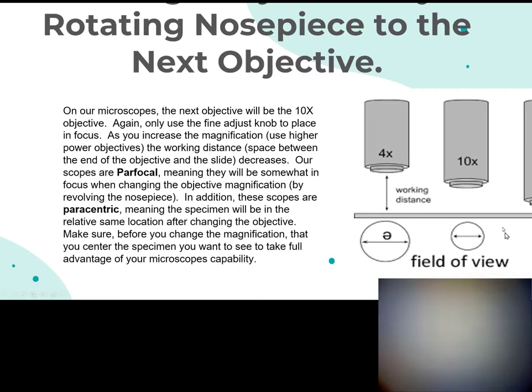Two terms I want you to know: parfocal means that when I start at 4x and swing the objective to 10x, it'll be somewhat in focus already. Paracentric means that when I move the stage to find a group of cells and then switch to the next objective, they'll be in pretty much the same position in the field of view. These are features we pay extra money for — it's a huge amount of work to try to overcome not having them.